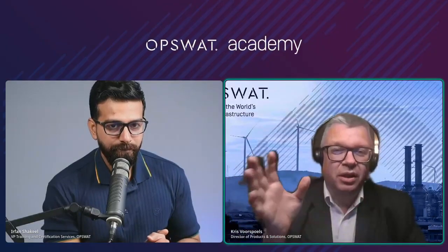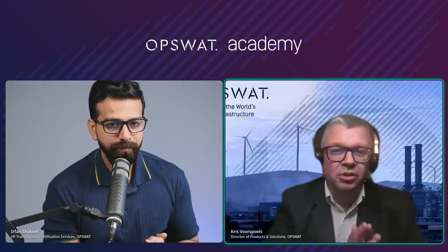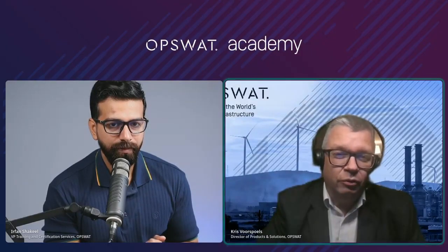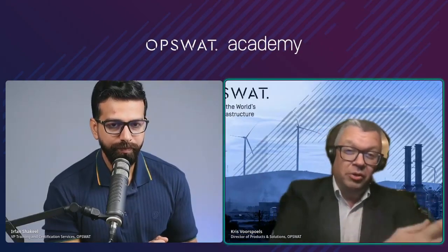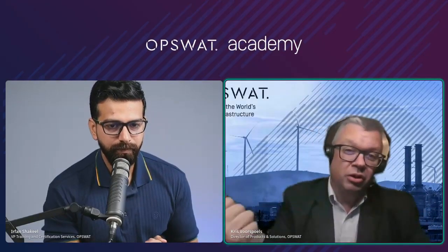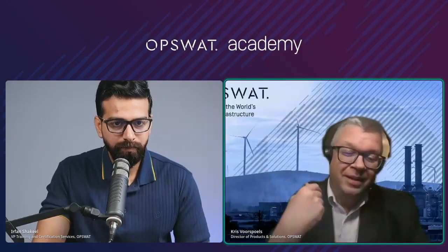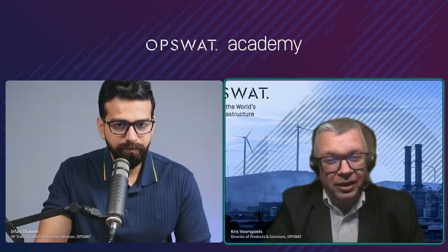For the most critical environment, that is the best advice I can give you. If you can make everything monitoring only, that is the best security profile. It's like everything is closed. Now, in real world scenarios, it's not always like that. You cannot always convert everything into monitoring only applications. So from 100% secure, one monitoring only, there are a few steps which can go in the other direction, allowing different communication streams to go in and potentially go bidirectional. And then it becomes really interesting how to protect those.